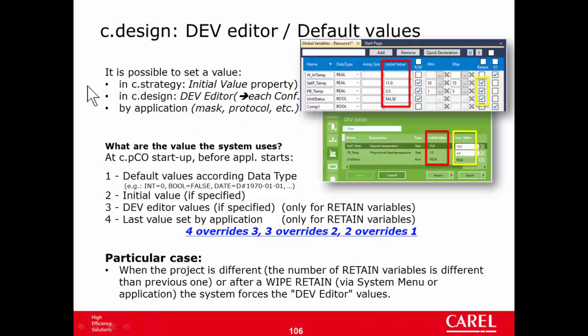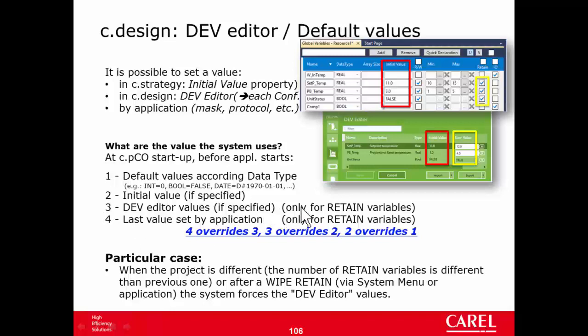So here you see only the variables that are in retain. Then by application — for example, we can change the setpoint in the mask. In the previous exercise we also changed it via protocol, via Modbus Master/Slave. So there are three ways. At startup, before the application starts, all variables take a value that depends on the data type — in general it's zero for all boolean, integer, and real variables. After that they take the initial value if specified, then the DEV Editor value if specified — available only for retain variables.